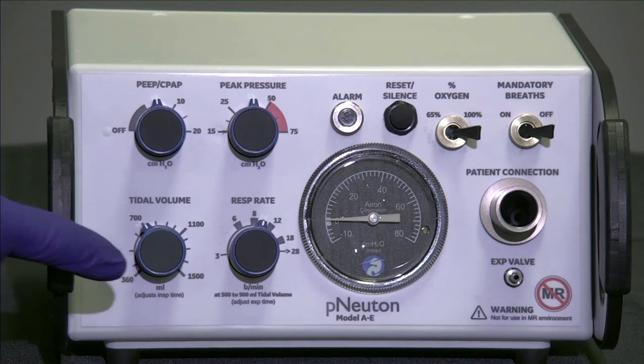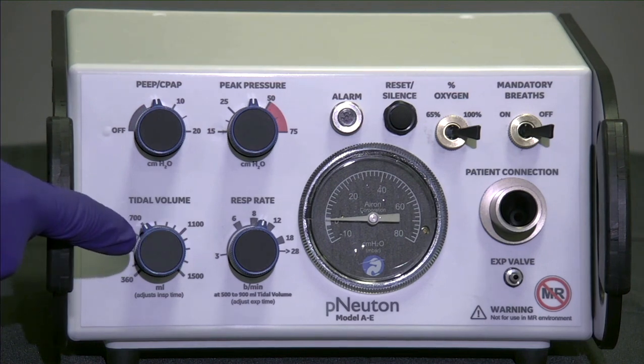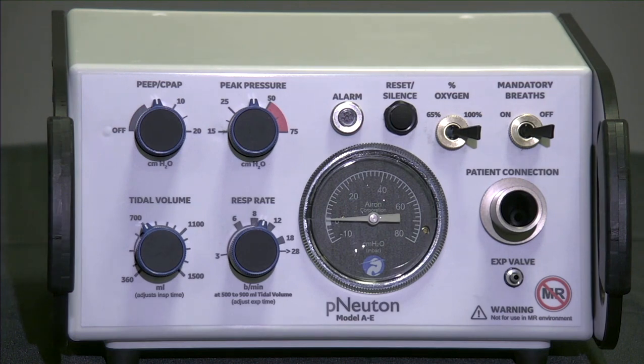Tidal volume control. The tidal volume control has a range from 360 to 1,500 milliliters for adult and pediatric patient needs. The pNeuton A-E uses a preset flow at 36 liters per minute for mandatory breaths. The tidal volume has been calibrated for patient delivery independent of changes in patient condition.